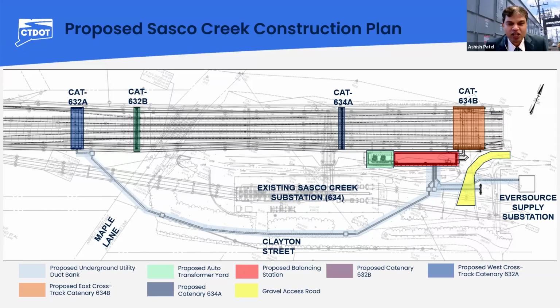The light green color block represents the proposed location of the auto transformer. The new auto transformer yard will be designed on the west side of the balancing substation. The new retaining wall will be designed to support a total of 2 new auto transformers. The retaining wall will also serve as a fall protection, and it will have an 8 feet high chain link fence on the top. The southeast side yellow color represents the new asphalt driveway over the existing gravel driveway. An 18-inch corrugated metal pipe will be replaced under this driveway.